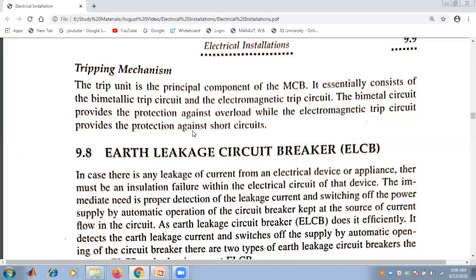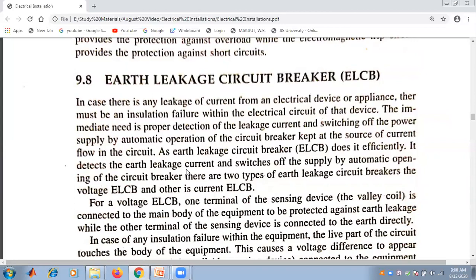Another portion of our discussion is the earth leakage circuit breaker, that is ELCB. If there is any leakage of current from an electrical device or appliance, there must be an insulation failure within the electrical circuit of that device. The immediate need is proper detection of the leakage current and switching off the power supply by automatic operation of the circuit breaker at the source of current flow. This device is named earth leakage circuit breaker.